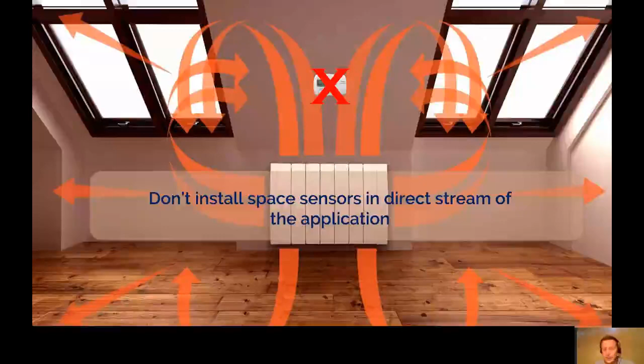We've got a couple of air conditioning units here providing heating, with a sensor on the side there. Next to that, a printer will get put underneath. The printer itself will emit a lot of heat, and the problem with that is when you put heat across a sensor, you tend to get a mix of heating and cooling coming from the same unit, which isn't ideal since you're going to get heating and cooling both happening at the same time. The occupants are not going to be happy, and your energy certainly won't be happy either, because you're working a lot more and never going to satisfy the set point.